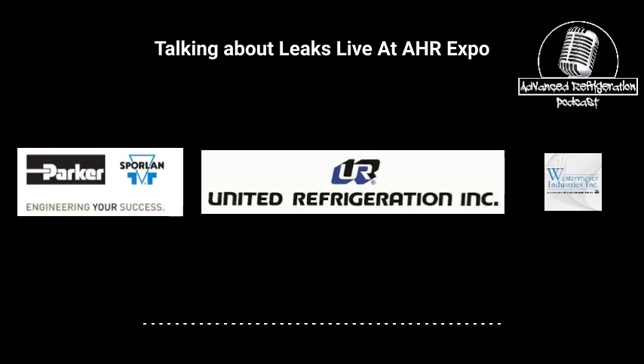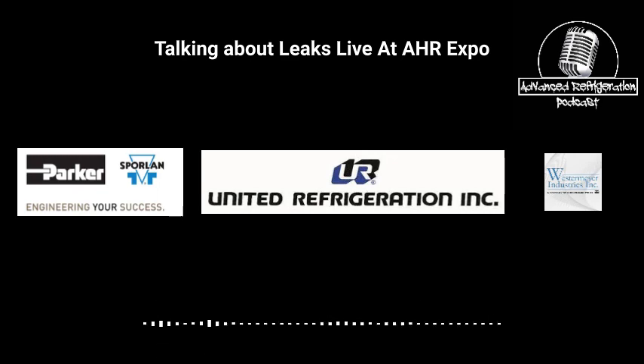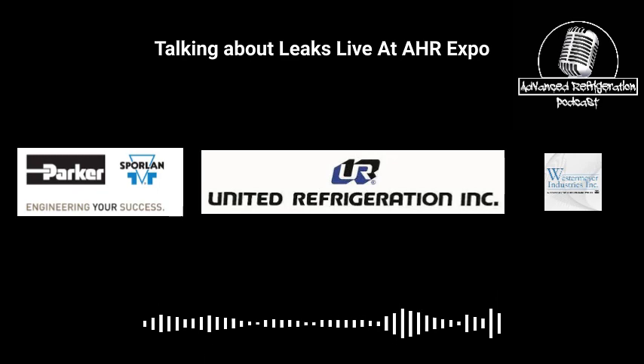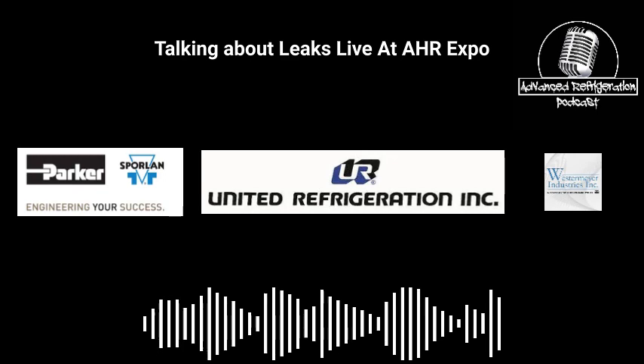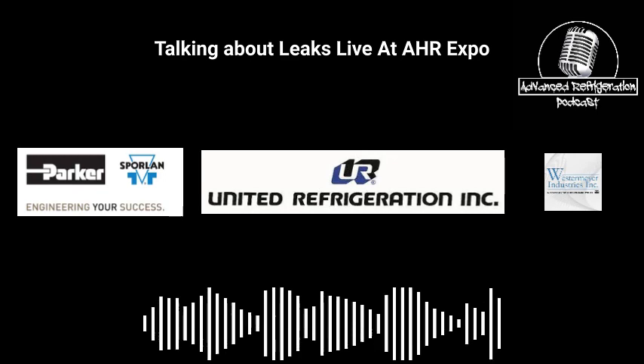He's like, do you know where it would leak on a lot of rack stuff? I'm like, Kevin says almost every single rack that he's ever gotten in has had a transducer. Also packing. Yep. Packing on valves is one of the worst ones. So I was doing a training thing over in Texas somewhere, and we were going over this LMP rack, and as I'm going through it, I'm like, oh yeah, here's the liquid injection. As soon as I muttered the word liquid injection, all of a sudden there was a white cloud that started spouting out above, and they're like, did you do that on purpose? I'm like, yes, I'm a wizard. No, but the packing was just super loose.